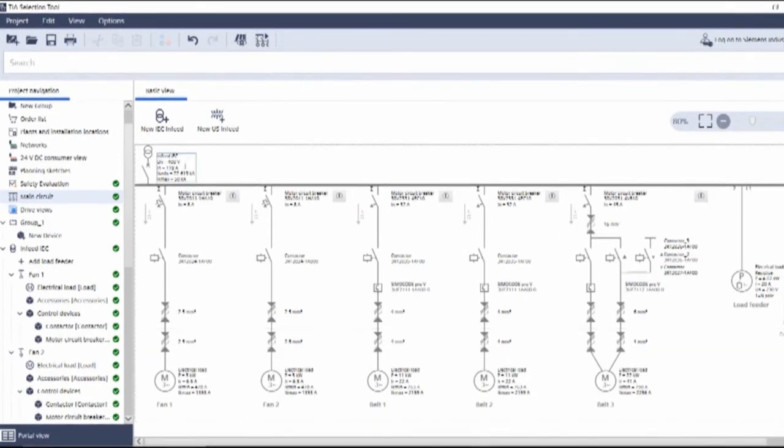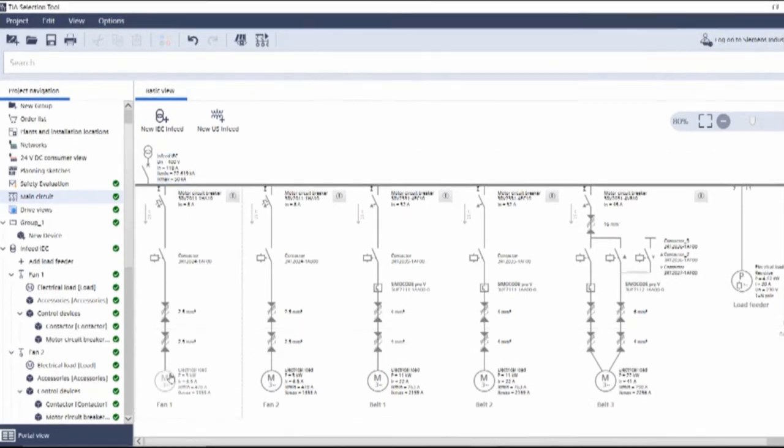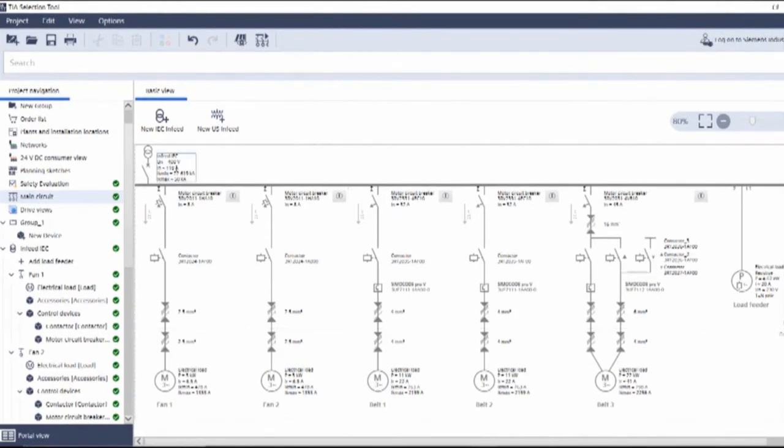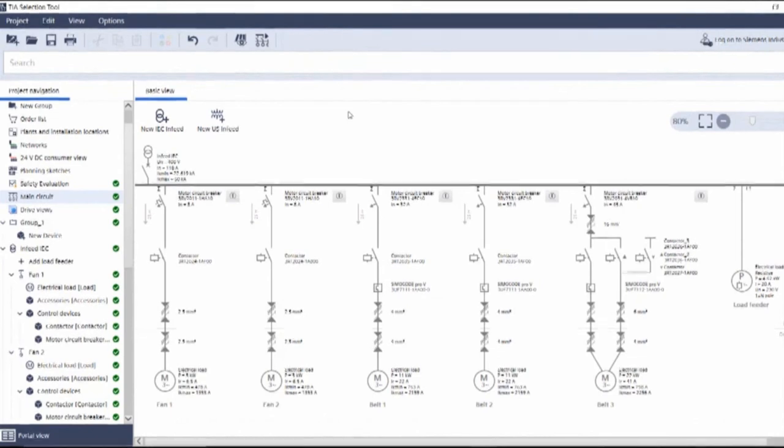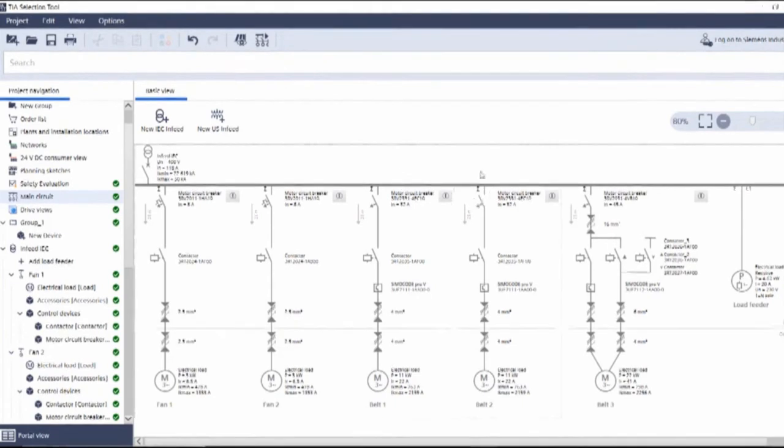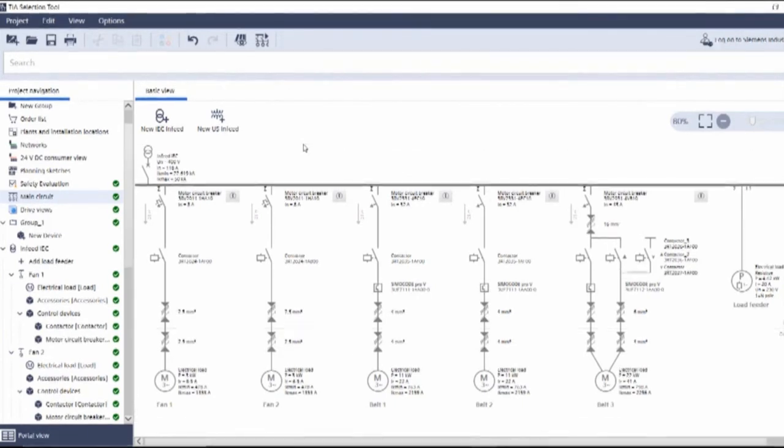Not that it's just that. Looking here, we've got the IK-Min, IK-Max, SCCR in total. And we've also got that for each branch here. We've got the total current. So we can go ahead then, based on this information and size, our feeder protective device, molded case circuit breaker, for example. So all of this, all in a touch of a few buttons, but it's not just that. There's a lot more this tool offers as well.